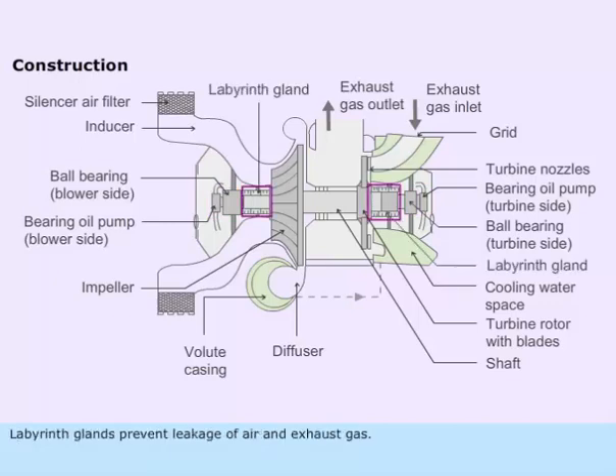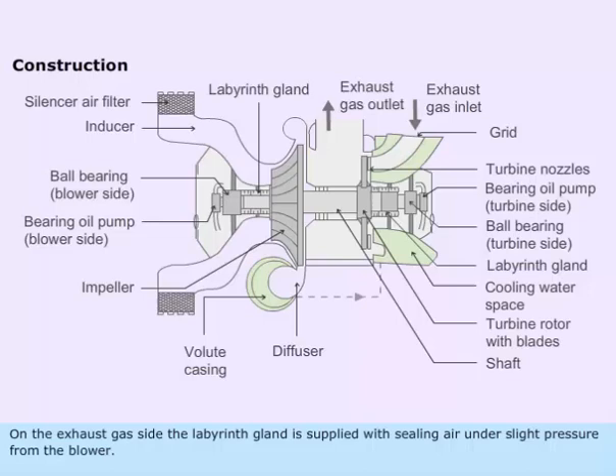Labyrinth glands prevent leakage of air and exhaust gas. On the exhaust gas side, the labyrinth gland is supplied with sealing air under slight pressure from the blower.